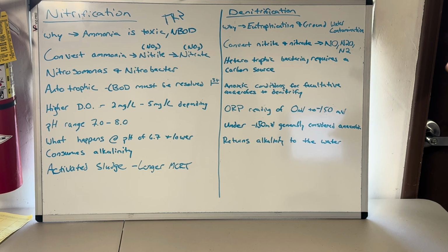Okay, a target would be, I've read, 8 to 15 days. 8 seems a little light to me still. I would buy 15 days. I would say 15 to 20. There's some extended aeration plants that get to 30 days. It's quite a while. And you might say, well, Shawn, what do you run? What's your MCRT? I couldn't tell you because I don't run those here.